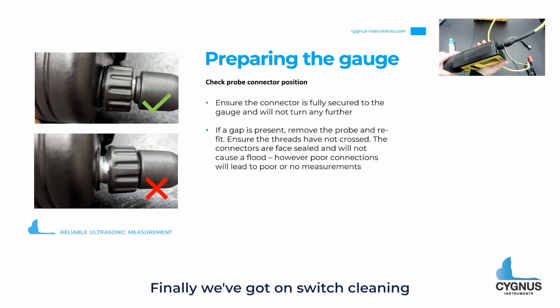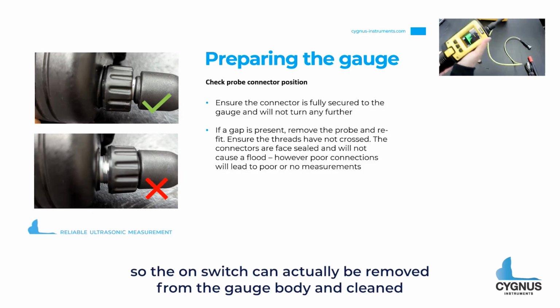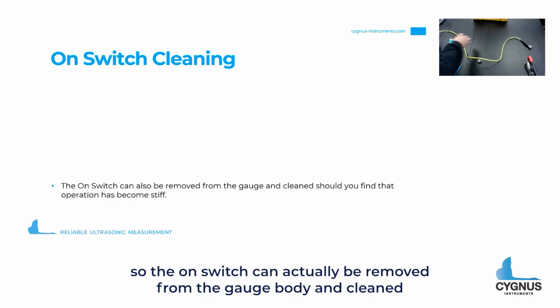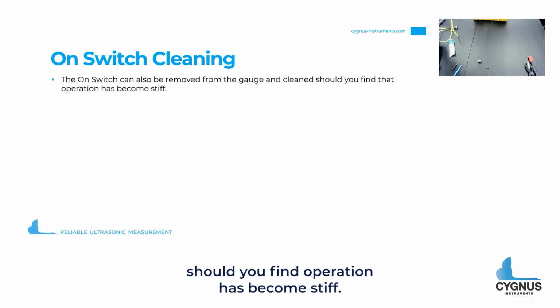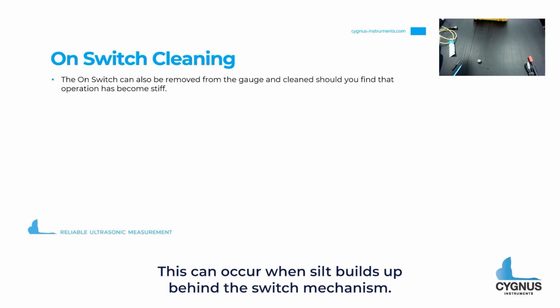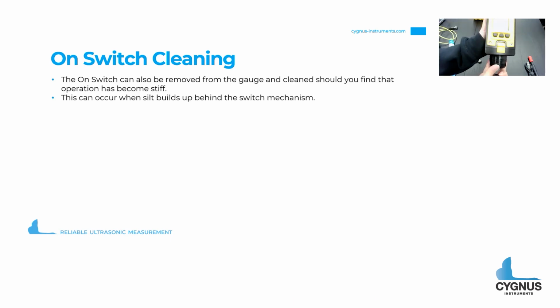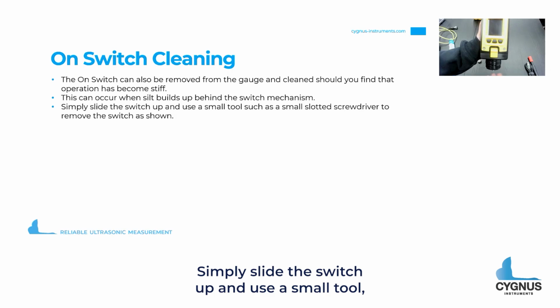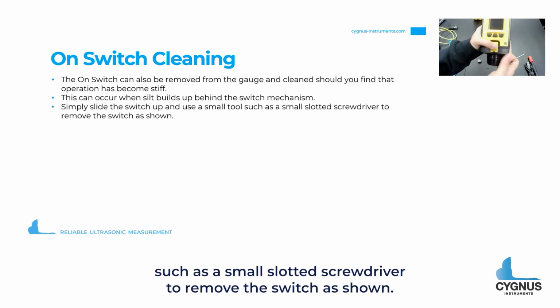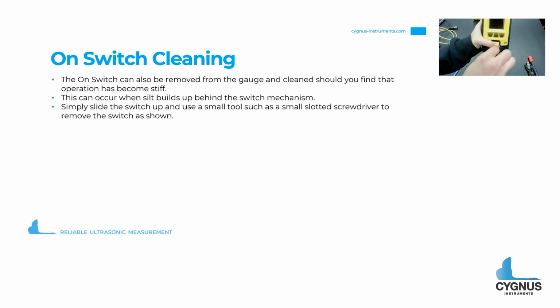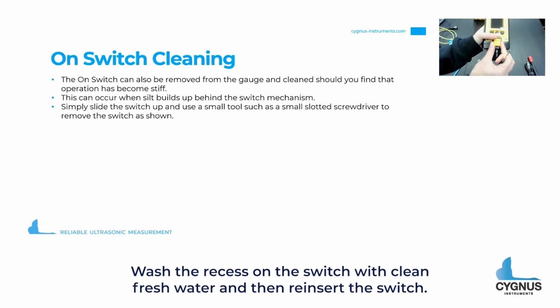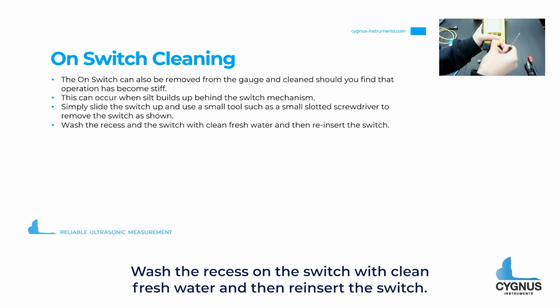Finally, we've got on-switch cleaning. The on-switch can actually be removed from the gauge body and cleaned should you find operation has become stiff. This can occur when silt builds up behind the switch mechanism. Simply slide the switch up and use a small tool such as a small slotted screwdriver to remove the switch as shown. Wash the recess and the switch with clean fresh water and then reinsert the switch.